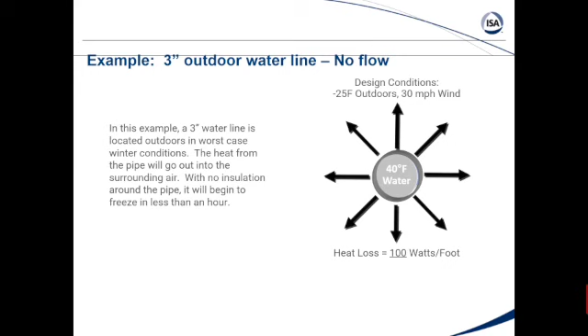One is to reduce the heat loss, and 2 is to make sure the energy coming out of the heating cable doesn't simply dissipate to the air. It's actually getting into the pipe. So now we look at a pipe that's insulated only and not heat traced. And often people will assume, especially in the residential, I get that all the time, it's like, oh, it's not going to freeze, it's insulated. Insulated will slow down the process of freezing, but it will not prevent it from freezing.